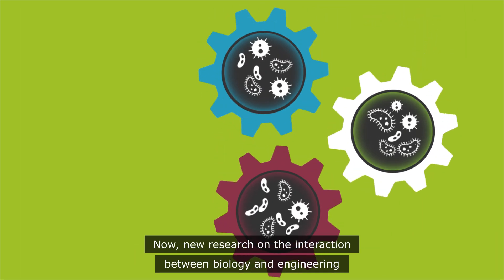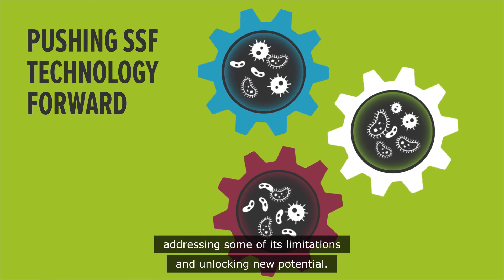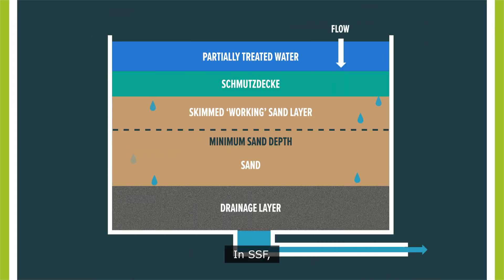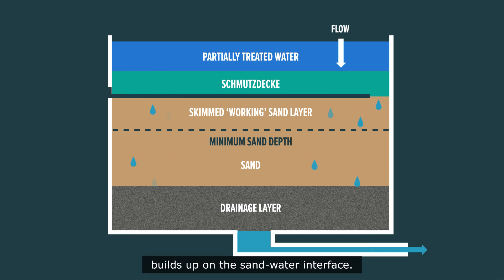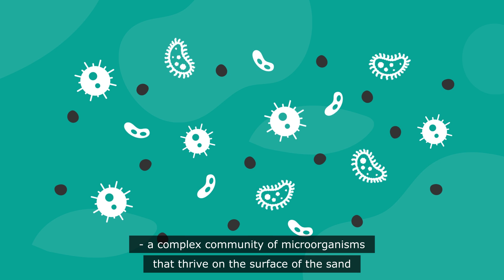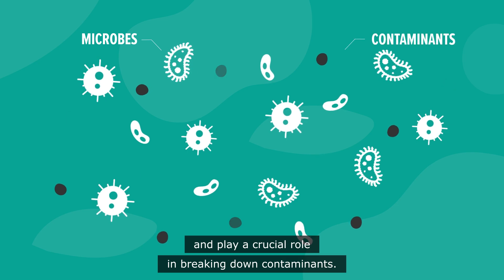Now new research on the interaction between biology and engineering is pushing SSF technology forward, addressing some of its limitations and unlocking new potential. In SSF, a layer of organic and inorganic material known as the Schmutzdecke builds up on the sand-water interface. This layer is essentially a biofilm — a complex community of microorganisms that thrive on the surface of the sand and play a crucial role in breaking down contaminants.